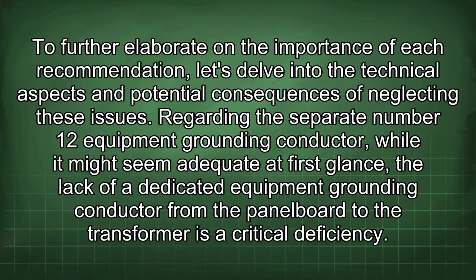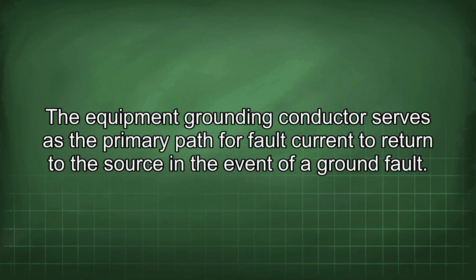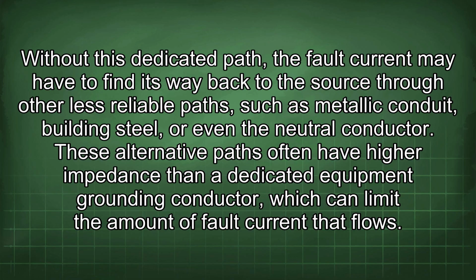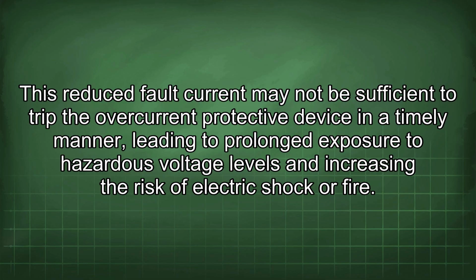To further elaborate on the importance of each recommendation, let's delve into the technical aspects and potential consequences of neglecting these issues. Regarding the separate number 12 equipment grounding conductor, while it might seem adequate at first glance, the lack of a dedicated equipment grounding conductor from the panel board to the transformer is a critical deficiency. The equipment grounding conductor serves as the primary path for fault current to return to the source in the event of a ground fault. Without this dedicated path, the fault current may have to find its way back to the source through other less reliable paths such as metallic conduit, building steel, or even the neutral conductor. These alternative paths often have higher impedance than a dedicated equipment grounding conductor, which can limit the amount of fault current that flows. This reduced fault current may not be sufficient to trip the overcurrent protective device in a timely manner, leading to prolonged exposure to hazardous voltage levels and increasing the risk of electric shock or fire.